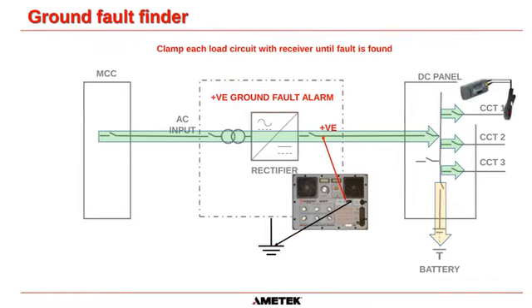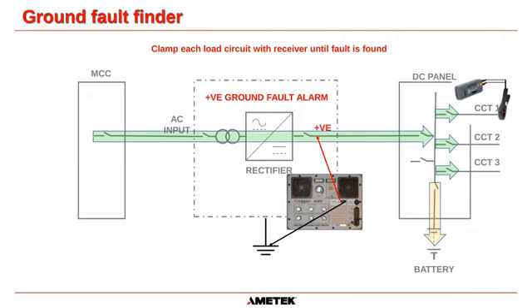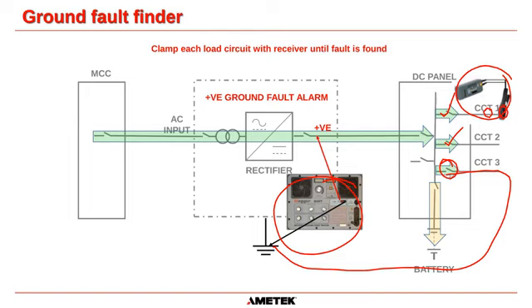And then what you can do is take the receiver side of the Megger, which is tuned to the exact frequency that the signal generator is sending, and you can use an amp clamp style receiver and put that amp clamp receiver around this circuit here. And the BGFT will tell you if there is a signal there or not. If there is no signal, then that does not have the ground fault. So let's say you don't see a signal on circuit 1, that is good. Circuit 2, no signal, that is good. You see a signal on circuit 3, that means that is where the ground fault is, because it's going down here and back to ground. And therefore you know that circuit 3 is the issue.